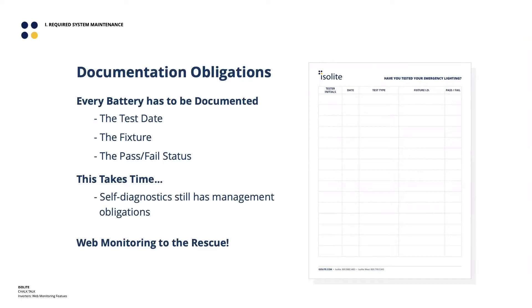Self-diagnostics can stop you from having to manually initiate those 30-second and 90-minute tests — the self-diagnostic device can run those tests on schedule for you. But the question becomes: how do you get that information and store it? For simple self-diagnostic systems, someone still has to go around and check all the little diagnostic LEDs to see what passed or failed. Even with self-diagnostics, it doesn't drive maintenance costs all the way down to zero — you still have to go on that scavenger hunt fairly frequently.